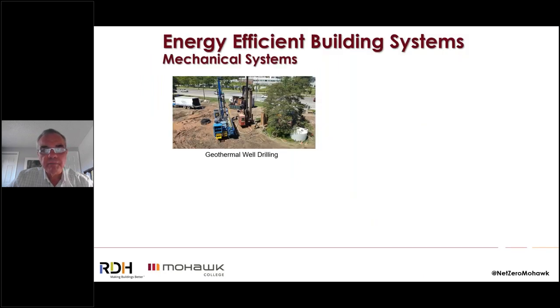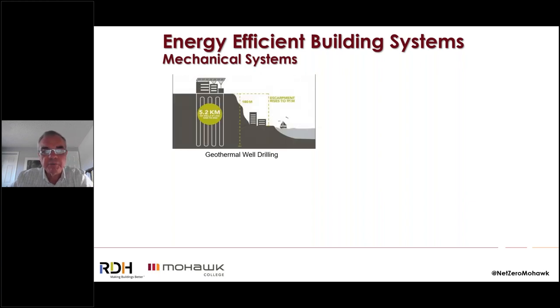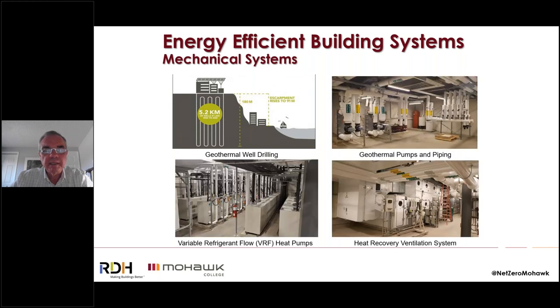The other component is the variable refrigerant flow geo-exchange system, now the common term. We had a lot of geothermal wells—28 of them, going down about 600 feet each, in four rows of seven, with a slinky system on top. I'll show you a picture of that. On the right-hand side is the pump system, fairly straightforward, and then the heat pumps up in the mechanical room—32 of them, very quiet operating and very efficient.